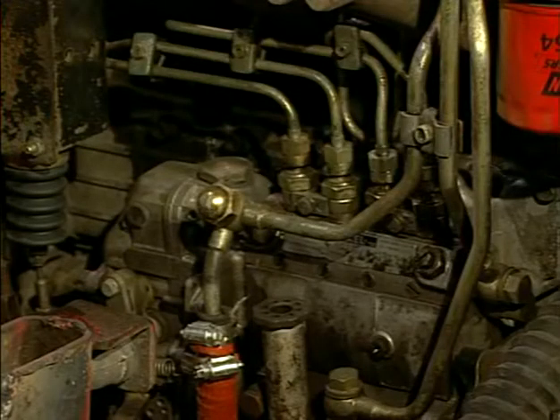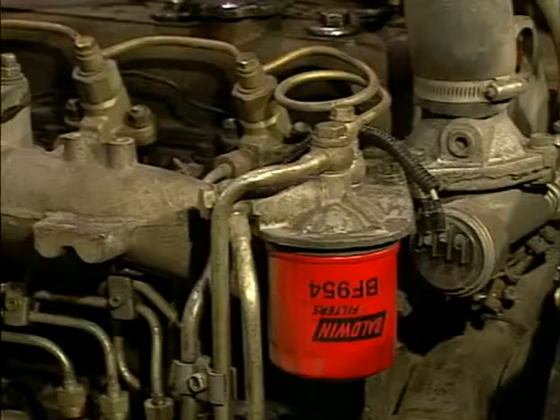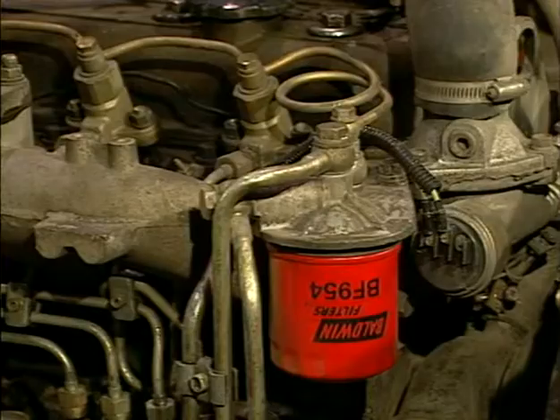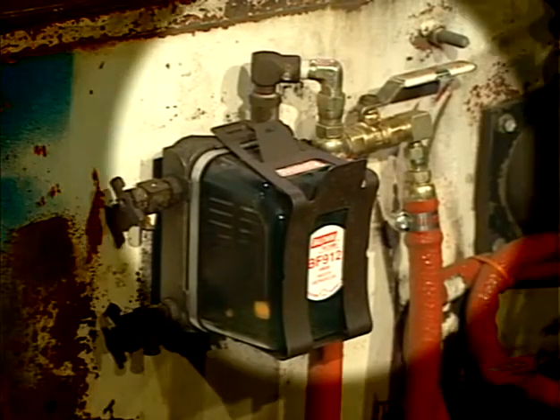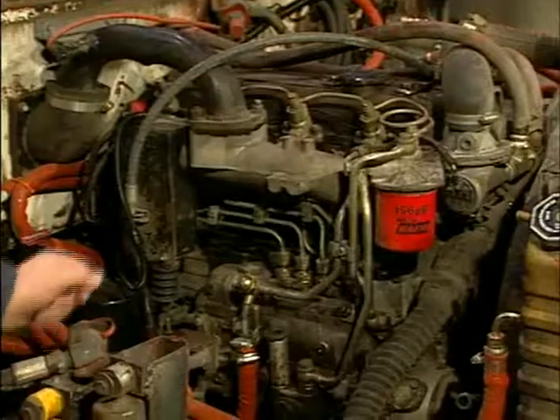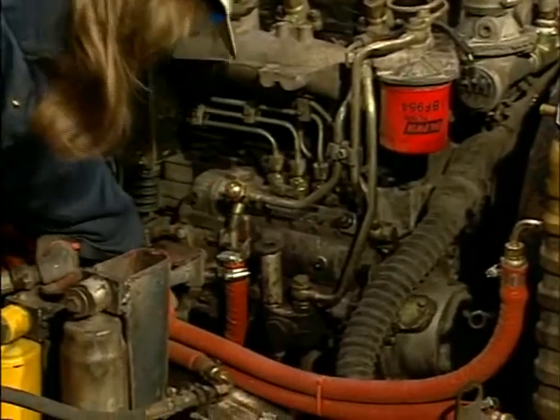These fuel lines are original engine manufacturer, or OEM, parts. What's important is to watch for leaks on all the fittings. Also, fuel lines must be separated from electrical wiring and protected from damage in ordinary use. The orange protective sleeves covering the fuel line need to be extended to cover the fittings to prevent any spray or leakage of diesel fuel from the lines to the fuel filter or separator.